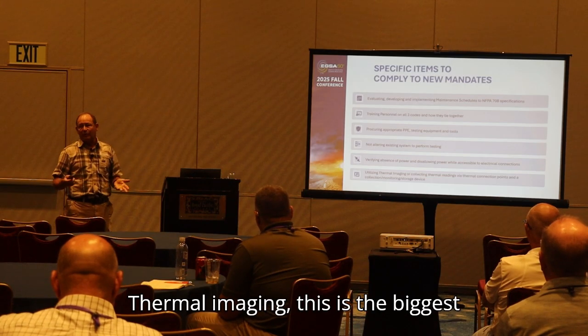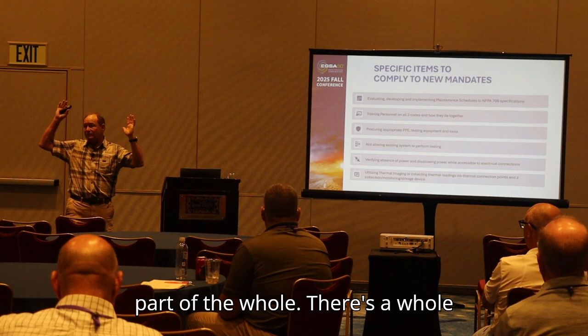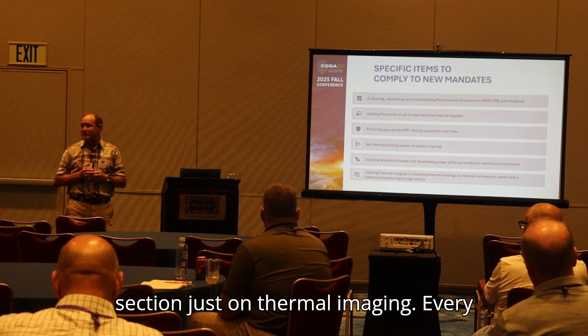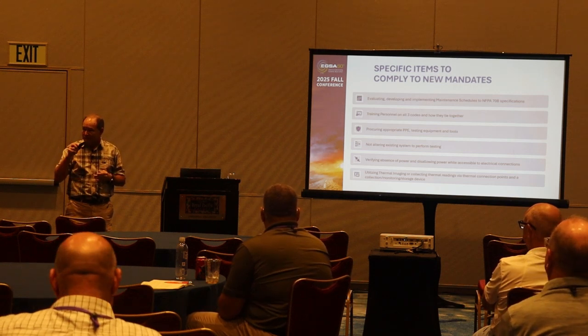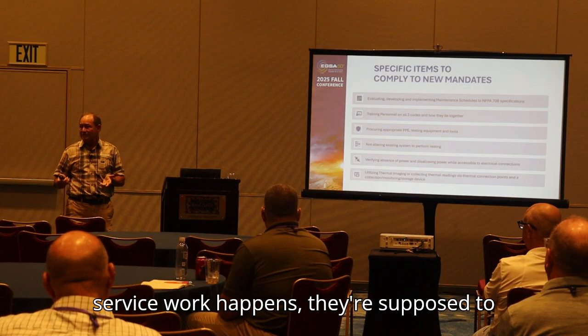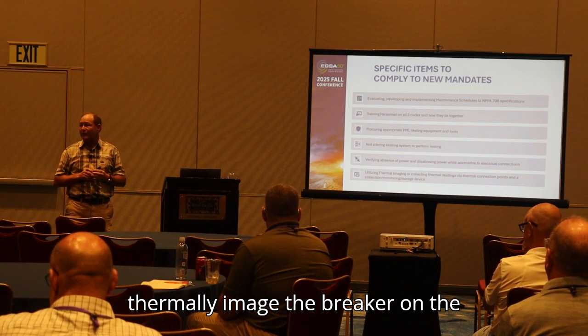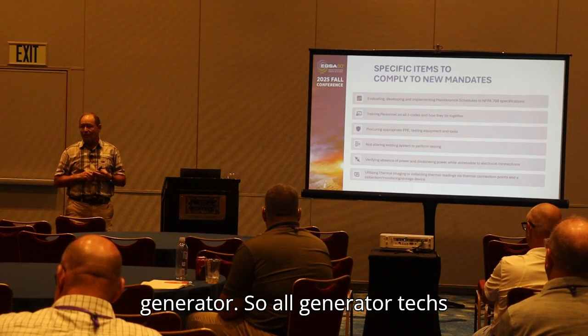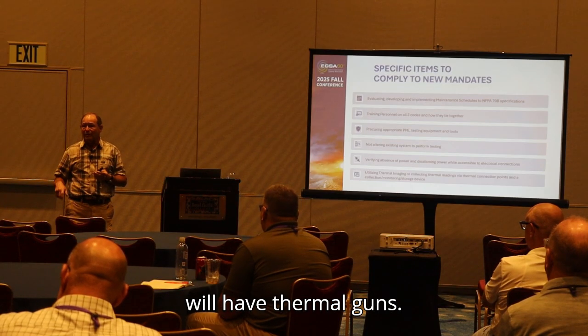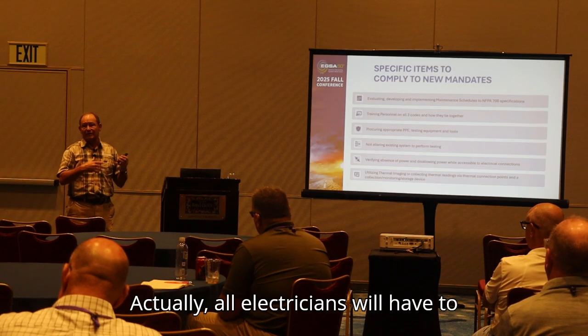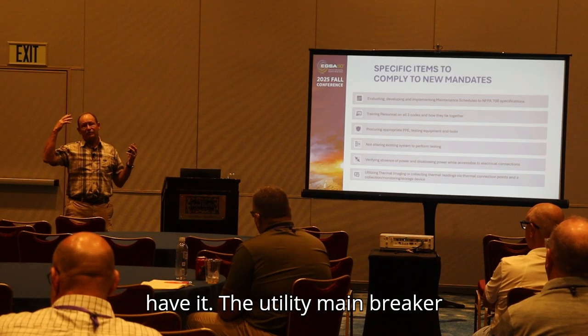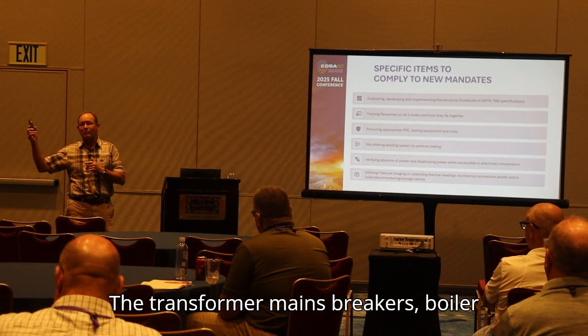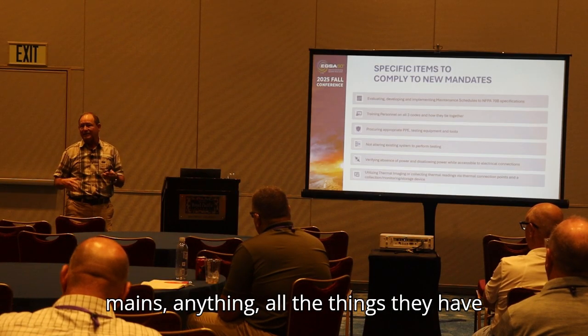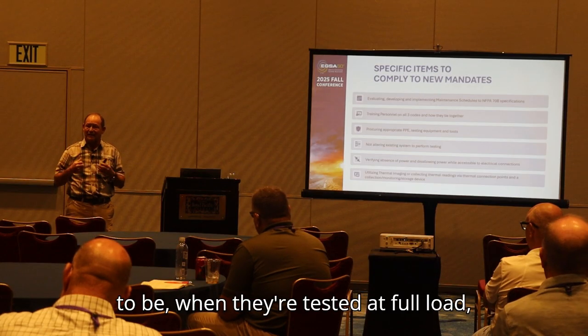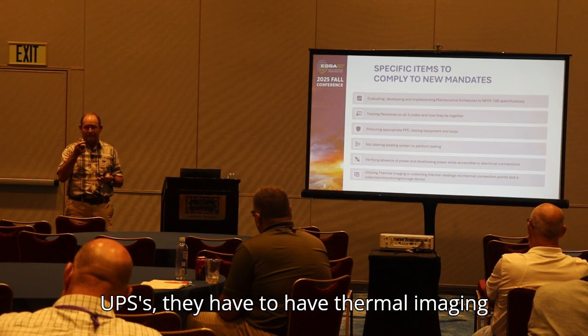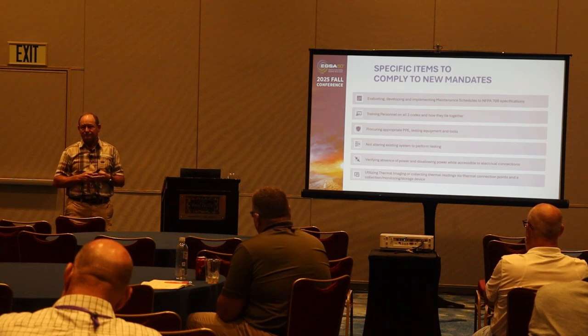Thermal imaging, this is the biggest part of the whole thing. There's a whole section just on thermal imaging. Every time a load bank or service work happens, they're supposed to thermally image the breaker on the generator. So all generator techs will have thermal guns. Actually, all electricians will have to have it. The utility main breaker, the transformer main breakers, boiler mains, anything, when they're tested at full load, UPSs, they have to have thermal imaging on them.